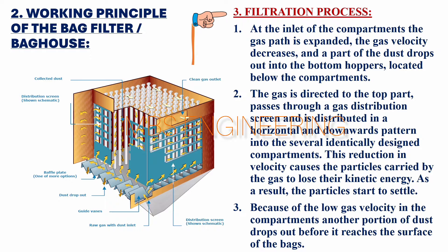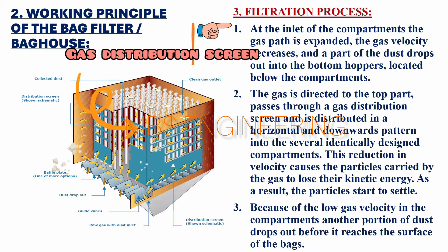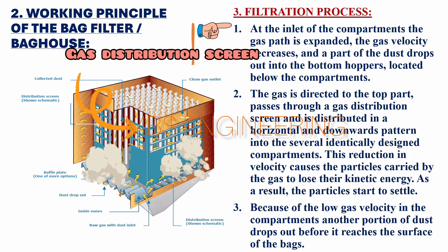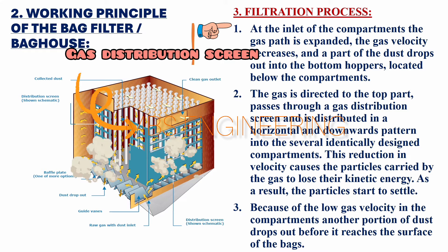Step 3 — Filtration Process: At the inlet of the compartments, the gas path is expanded, the gas velocity decreases, and a part of the dust drops out into the bottom hoppers located below the compartments.